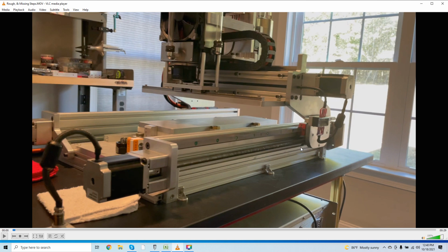Once we start documenting and seeing, okay, we've got this, like I said, we've isolated X, we've isolated the Z axis, and we see we've got this problem on the Y. At that point, after we've checked linearity on the X and Z axes, and isolated it on the Y, we then start breaking down the mechanical aspect of what could be causing the problem. Now, this is where things get really interesting.